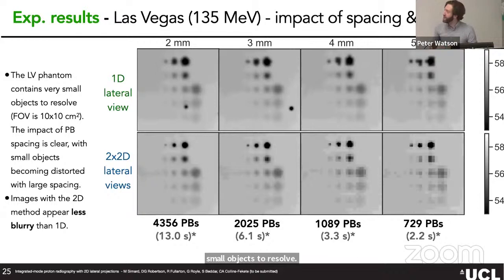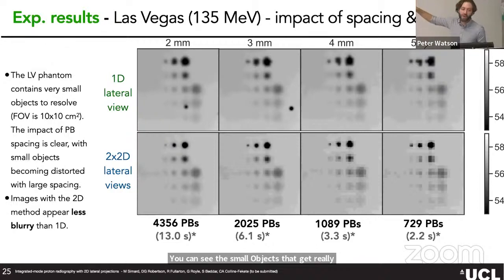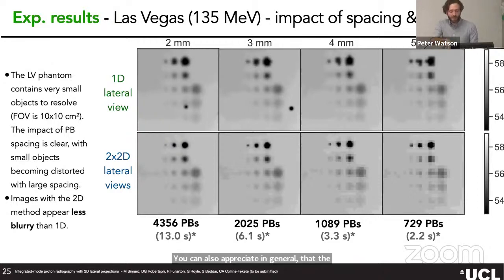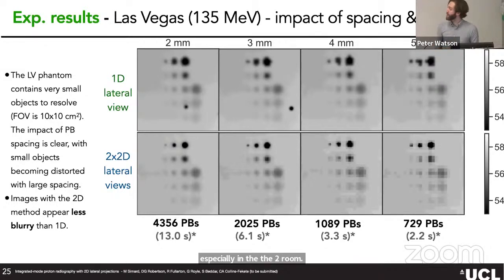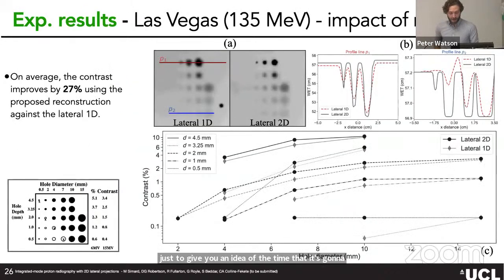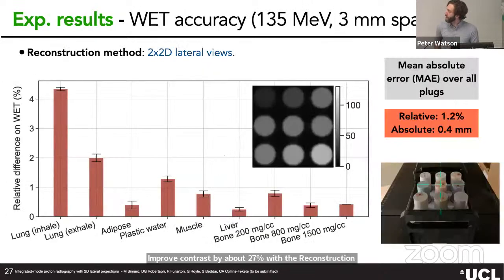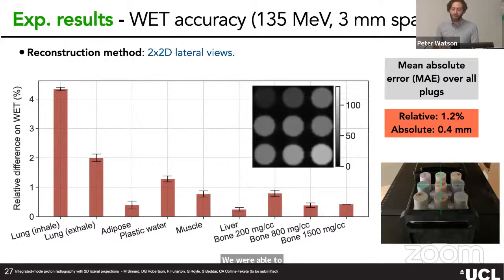For the Las Vegas phantom results, from left to right you have different beam spacings; from top to bottom, two reconstruction methods — the literature method on top and our developed method on the bottom. The Las Vegas phantom contains very small objects, and you can see the impact of pencil beam spacing clearly — small objects become distorted with larger spacing due to sampling issues. Our 2D method is noticeably less blurry than the literature method, especially in the 2 mm images.